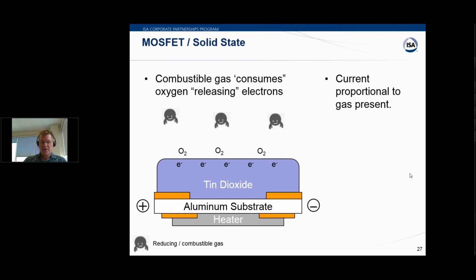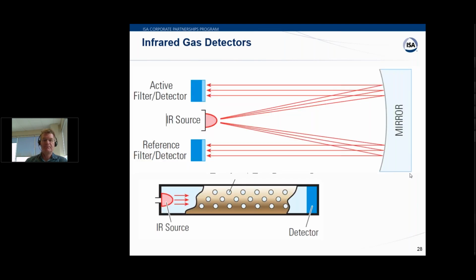Some of the things to remember, especially thanks for the question on response time, is that depending on your configuration, these detectors can take 20 to 90 seconds to respond, and they are best suited to relatively low humidities because they can only handle up to about 10% humidity. So there's something to just keep your eyes on. Then we have, and these are becoming more common, infrared gas detectors. And infrared can come in two shapes. The one on the bottom has an infrared source and then a detector. The gas would permeate through the little holes here in the path length, and then we would measure the concentration of gas over that short distance. The more common configuration is the double beam on the top.